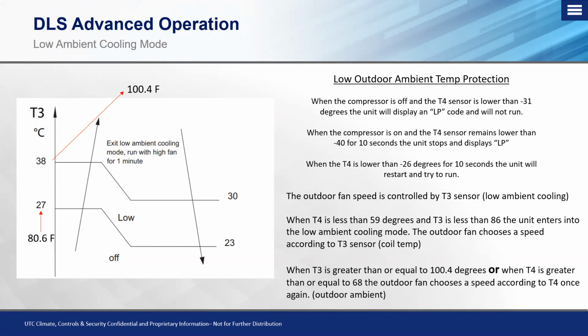When the T4 sensor is higher than -26 degrees for 10 seconds, the unit will restart and try to run. So what that means is, if that sensor for some odd reason was reading negative 40 for that 10-second period and shut down, when that sensor reads warmer than negative 26 degrees, or it starts to get warmer outside, for 10 seconds or longer, the unit will restart and try to run.